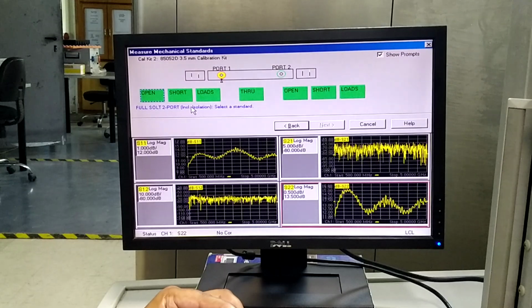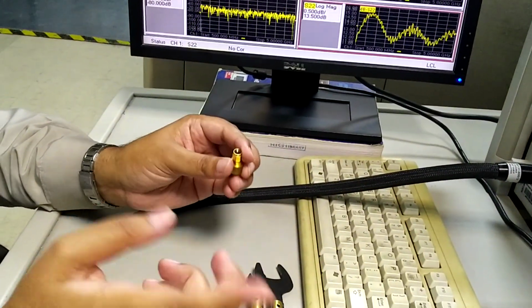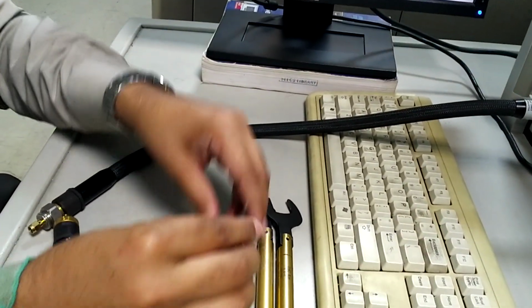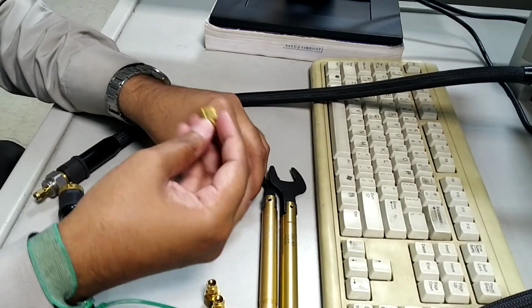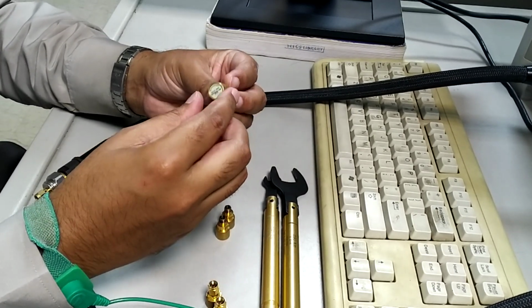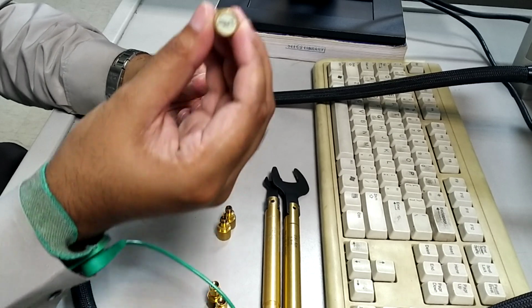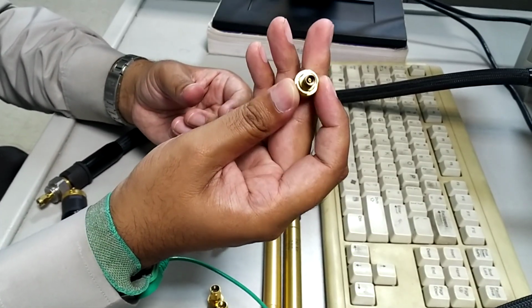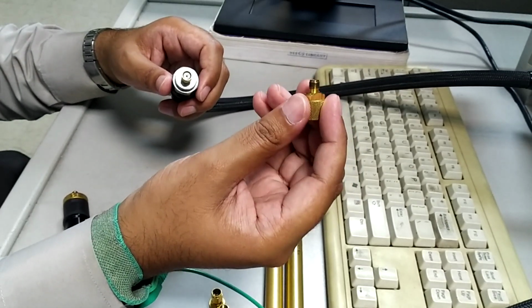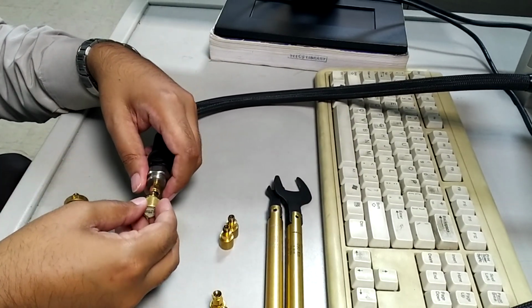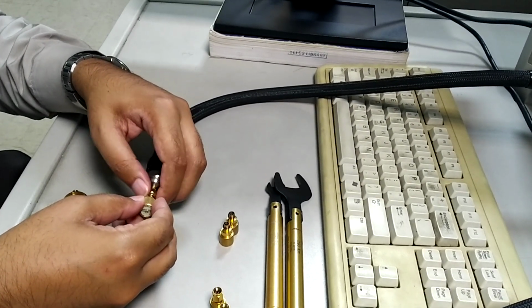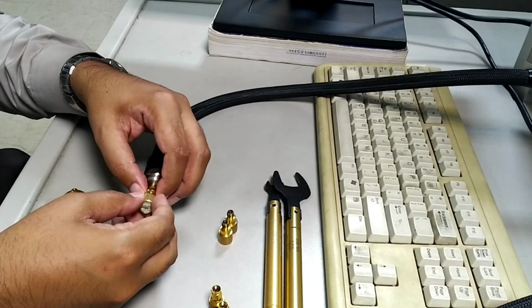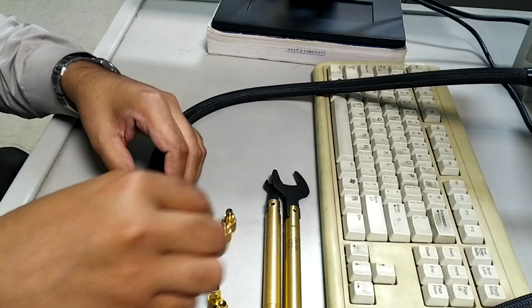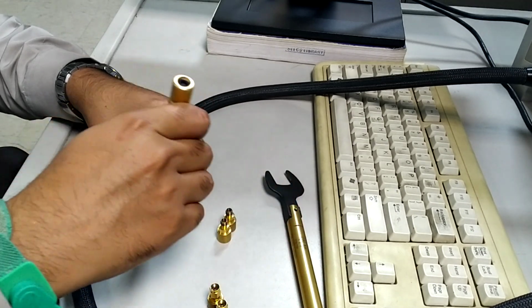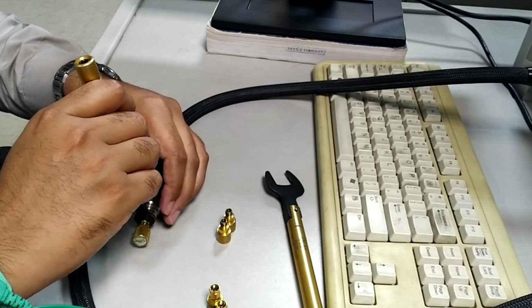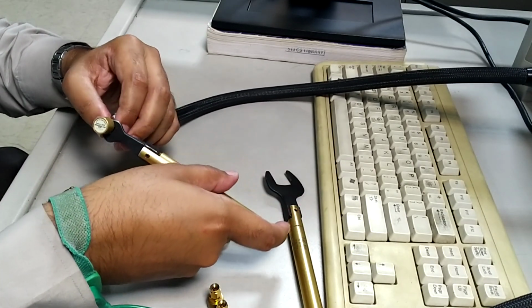The first standard that came in front of me is a short standard, a male. Since I'm using port number 1 first, I have to use the female standard. So I can use any standard. Here, going to port 1, the first standard that came to me is a broadband load standard. You can see here this is a broadband load standard, a female standard. I will start with port number 1. So I connect it here. I hope you can see the connection here. I use my hand to connect this definitely in the start, just to make the connection, and once it's connected, then I have to use this torque wrench to make sure that this standard is perfectly connected.